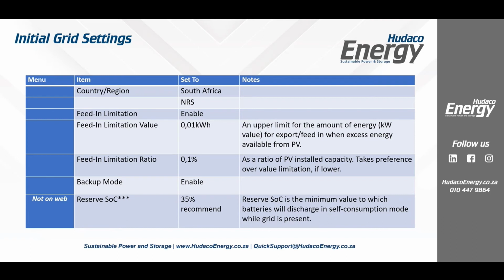Feed-in limitation, then we enable feed-in limitation value. Instead of setting to 0 and 0 like we would in disable, rather set them to 0.01 kilowatts and 0.1%. The reason we recommend that is there can be no divide by zero calculations, which might return an error at some point. So if we use these settings, it actually goes to zero. We don't actually export any. It assumes it is zero, but any calculations use a tiny amount. So this feed-in limitation we turn on. This is the upper amount of energy that it's allowed to export. This is actually kilowatts, not kilowatt hours. So 0.01 kilowatts, in other words 10 watts, you'd be allowed to export, or 0.1% of the installed PV capacity that we would put.